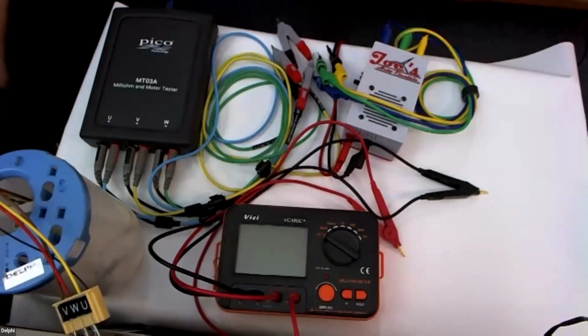But Toyota, for the first several years of the Prius, used Generation 2 with three-phase power going directly to the compressor. There was a miniature inverter board on the main inverter board, underneath that big cover on top of the earlier Priuses. So I have a version of one of those compressors, and we'll check the resistance phase balance with a couple different milliohm meters, the VC and the Pico.